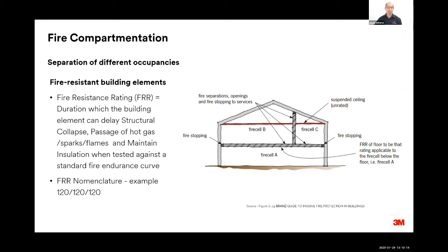So when we're talking about the separation of different occupancies or splitting up the building into fire cells, that's done with what we call fire separating elements. So that can be a fire rated wall or a fire rated floor or a ceiling that resists the incipient spread of fire. So we term the duration of fire protection that these provide the fire resistance rating. And the fire resistance rating is a duration, and I'll talk about that in a moment. But what you'll see is a number that in fact is a duration, and the duration is determined in most cases through testing against a standard fire test, a standard fire endurance test.